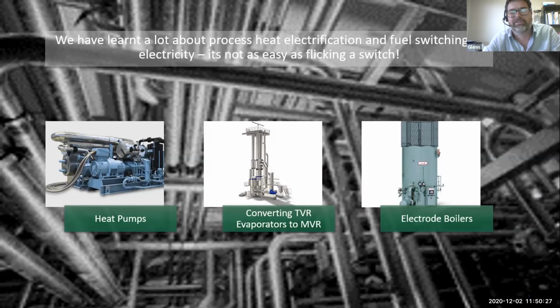Heat pumps, for example - what we found was that procuring, installing, and commissioning them would follow the project path we originally envisaged, and there was no great issue with any of that. But what we found was that the heat source for heat pumps does not always necessarily line up with the time that you need a heat sink. So the first thing we had to do was put in some kind of heat storage - a large tank somewhere with hot water in it, for example.